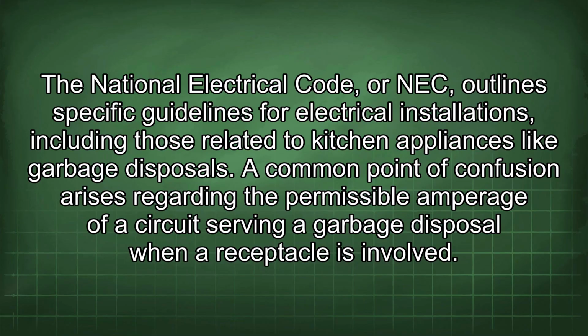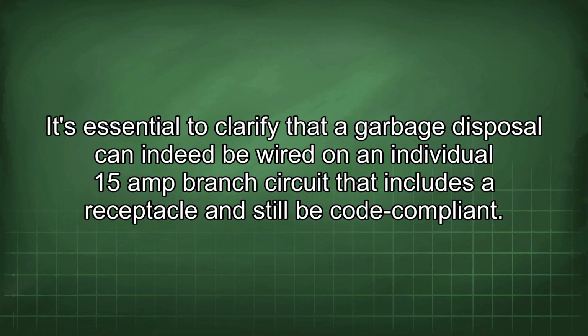The National Electrical Code, or NEC, outlines specific guidelines for electrical installations, including those related to kitchen appliances like garbage disposals. A common point of confusion arises regarding the permissible amperage of a circuit serving a garbage disposal when a receptacle is involved. It's essential to clarify that a garbage disposal can indeed be wired on an individual 15-amp branch circuit that includes a receptacle and still be code compliant.